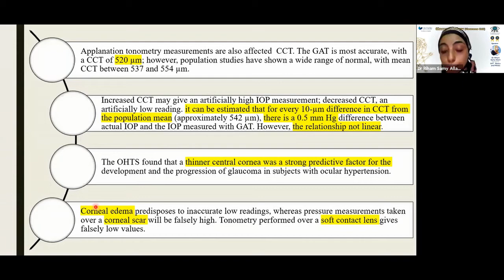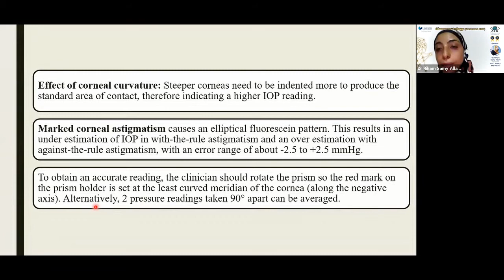Regarding the effect of corneal curvature, steeper corneas need to be indented more in order to get the proper circles, as we saw before. So the steep cornea tends to give a higher IOP, or overestimation of the pressure. This is seen in corneal astigmatic errors. So why does this occur? Because when we have a uniform cornea, we have a proper circular pattern, a proper circle, which we bisect into two hemispheres. However, when we have with the rule or against the rule astigmatism, this circle becomes an ellipse. So the area of contact between the tonometer and the cornea is not what we are assumed to know for the Goldmann applanation tonometry to get proper readings.